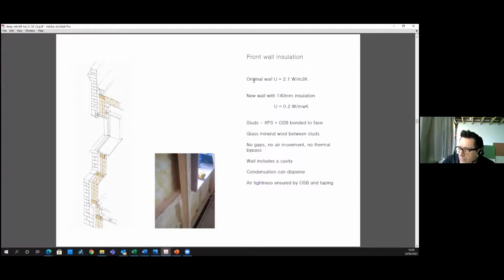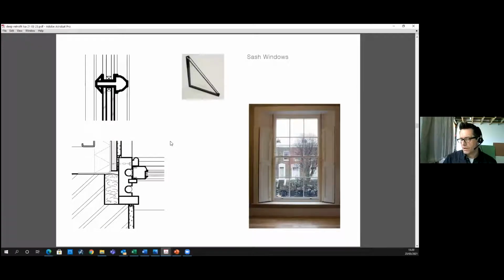And so we started off with a U value of around 2. Arguably that might be seen as better than that now, perhaps about 1.7. And with quite a lot of wall insulation, a U value in the proposed of about 0.2. So not far from building regs now. Pretty robust. And that's a replica sash window fitted into that wall insulation with the original shutters fitted back to it.